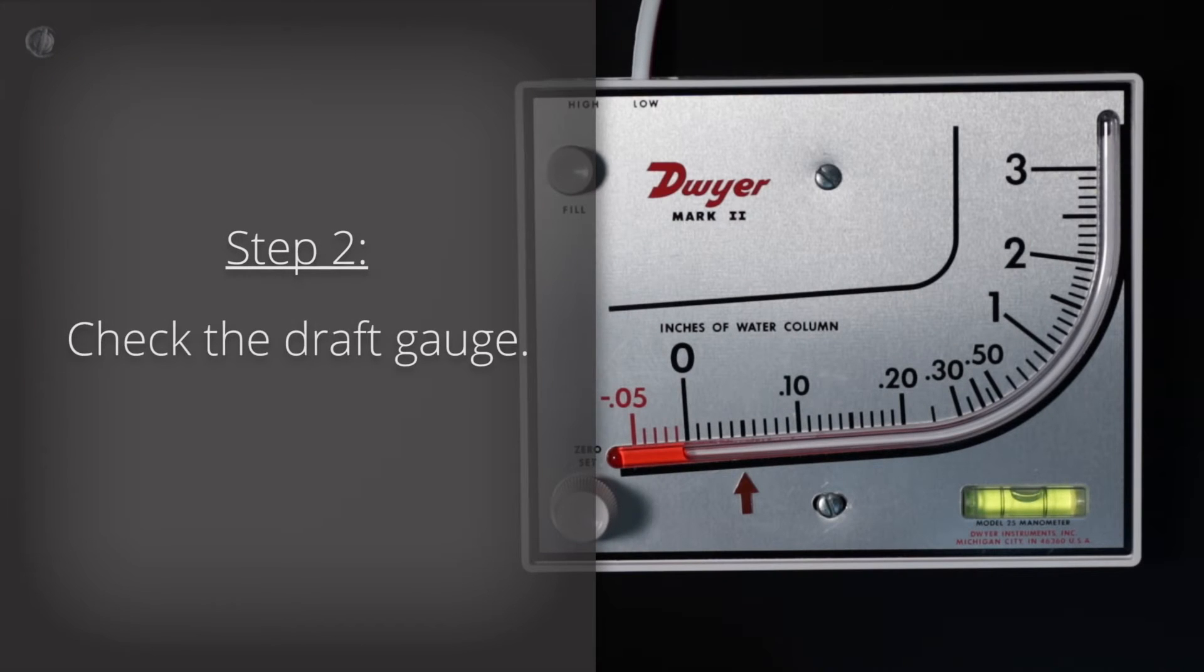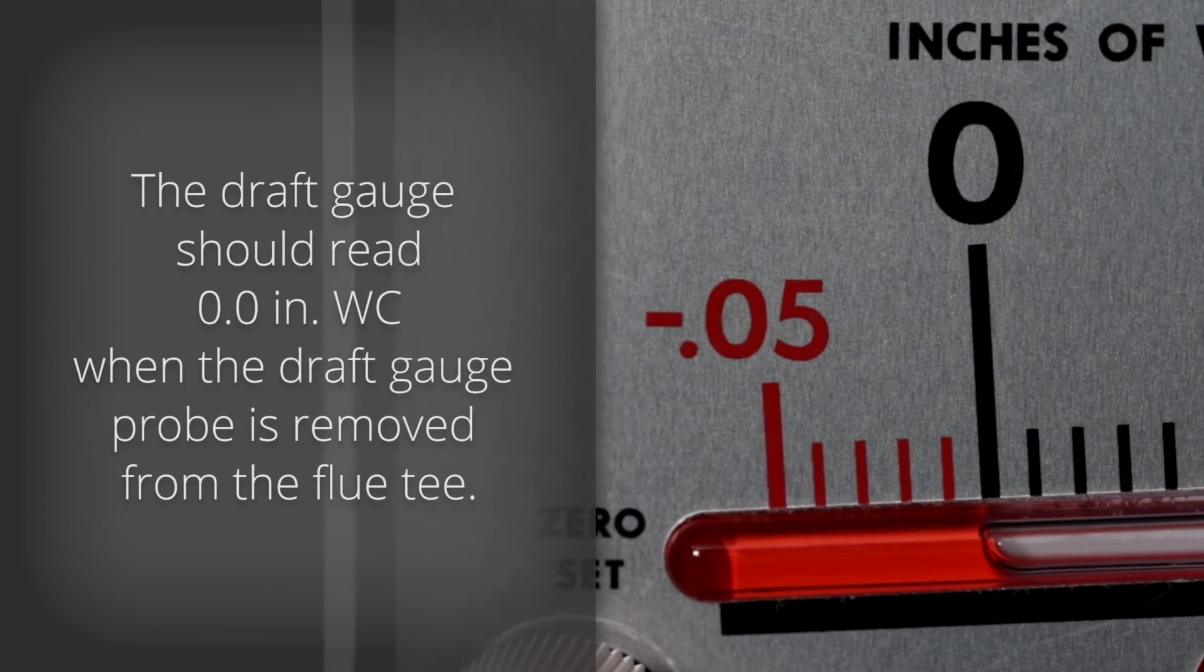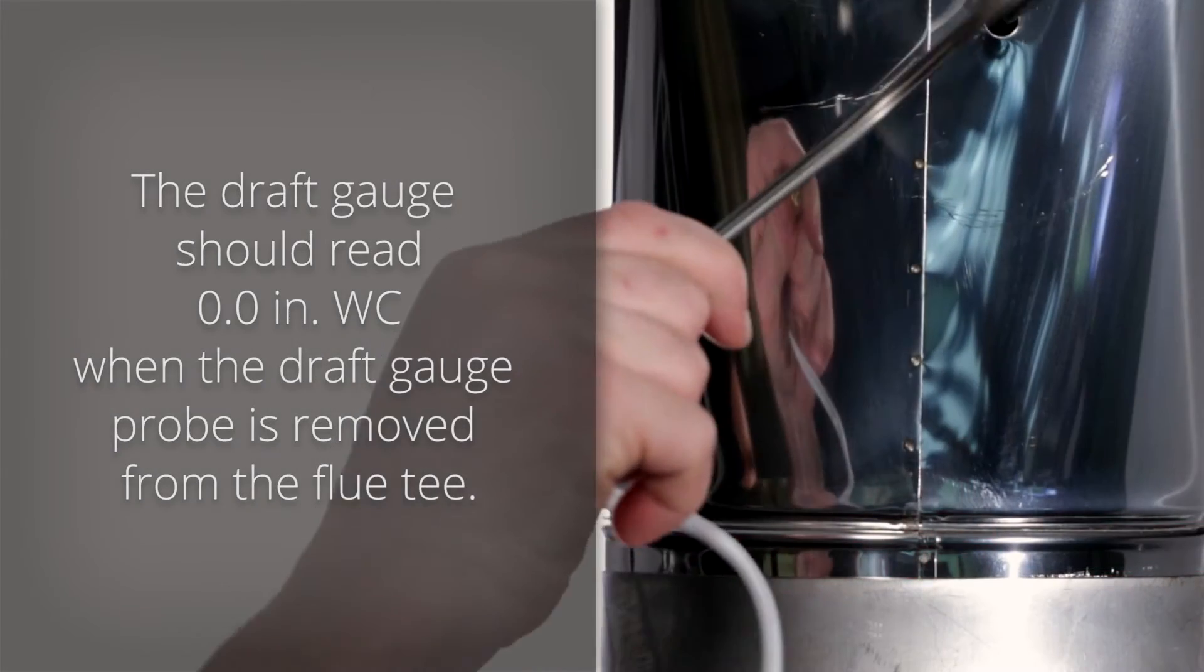Step 2. Check the draft gauge. Note that the draft gauge should read 0.0 inches of water column when the draft gauge probe is removed from the flue tee.